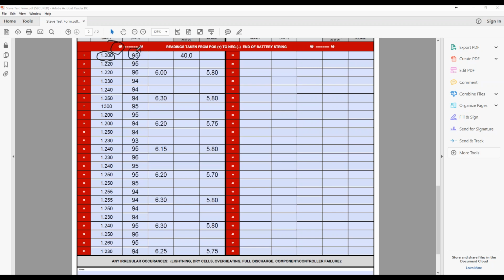Battery temperature - it's a good idea to have that infrared thermometer to measure the battery temperatures of the cells. A lot of times, if you're measuring 95, 95, 96, 94, 95, and then 102 or 110, that cell's running a lot hotter than the rest of the cells in the battery bank. That's an early indicator of something going on with that cell. It could be a warranty issue, it could be a non-warranty issue, or it could be the overall battery in the process of failing. Something to definitely look at.